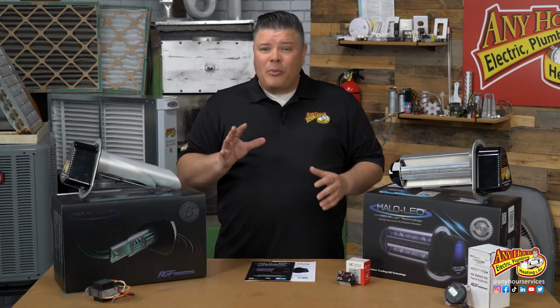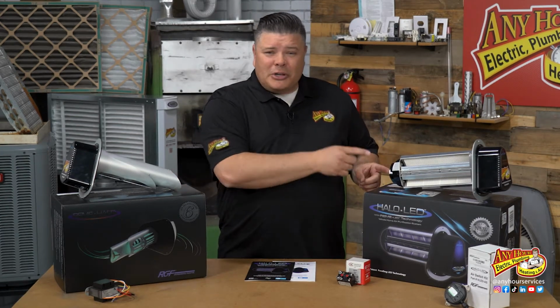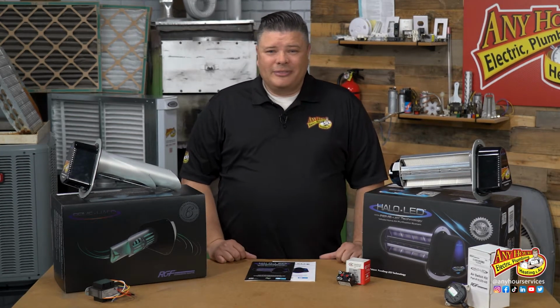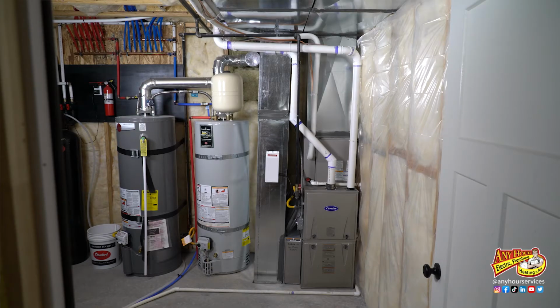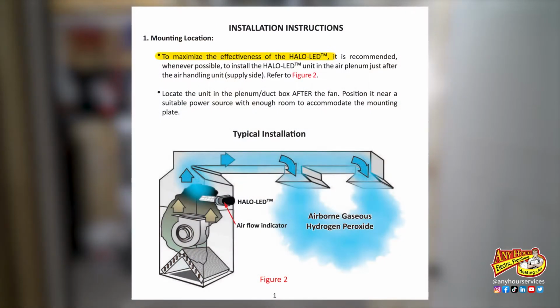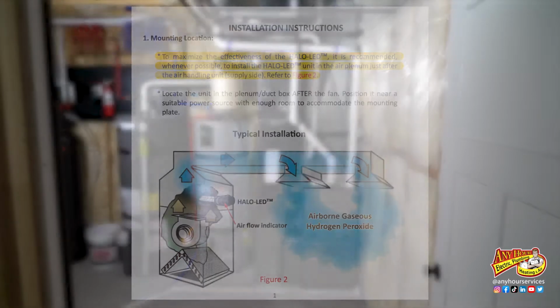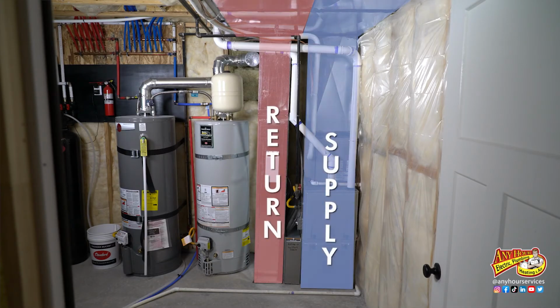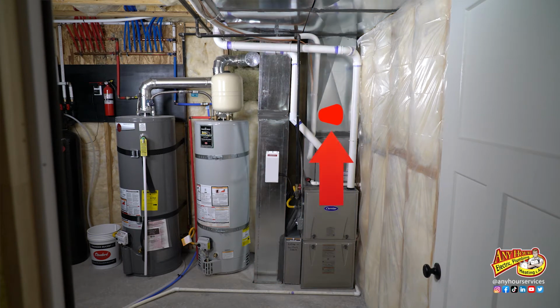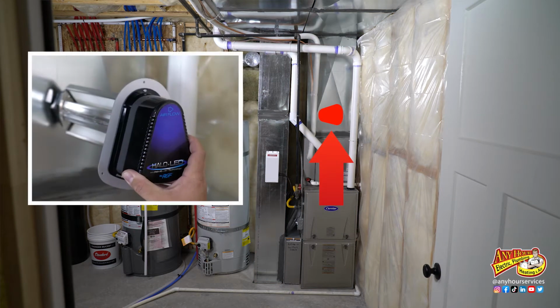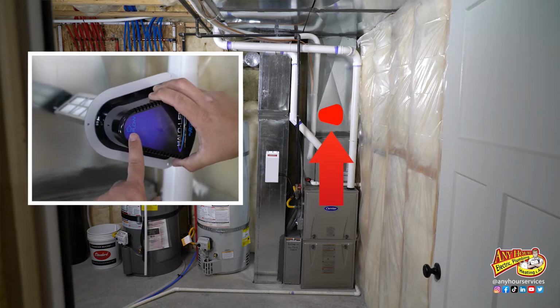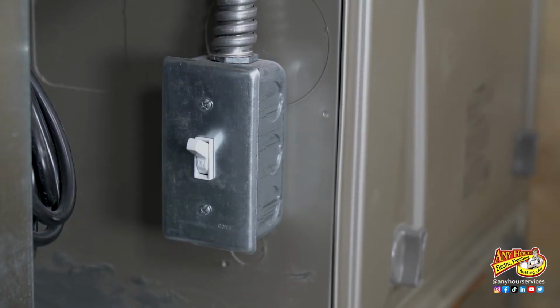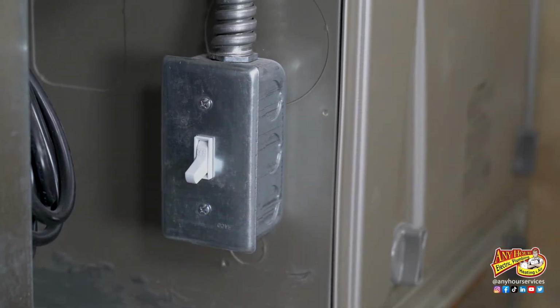Now, what you've all been waiting for, I've got a furnace out in the field. I'm going to show you how to install this Halo LED. To maximize the effectiveness of the Halo LED, it's recommended whenever possible to install in the supply plenum just after the air handler. So determine which is the supply side and identify where you have enough room to accommodate the mounting plate. Be sure to pay attention to the airflow direction arrow. Always be sure to cut power to the furnace before starting.